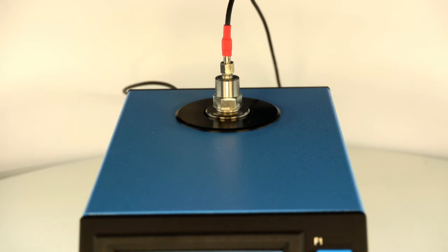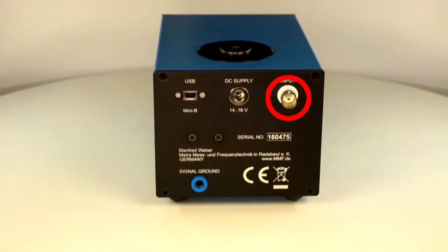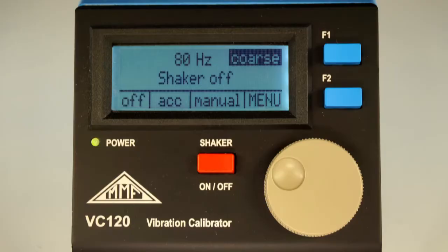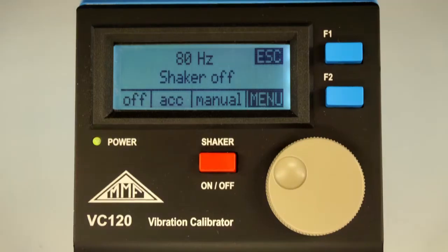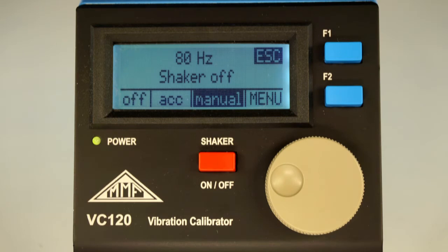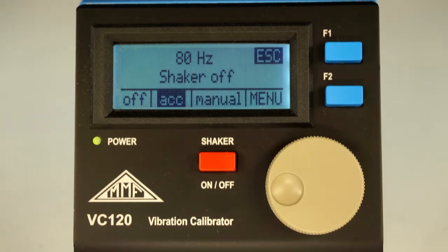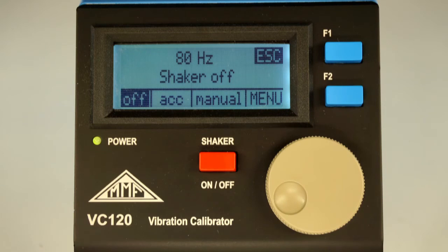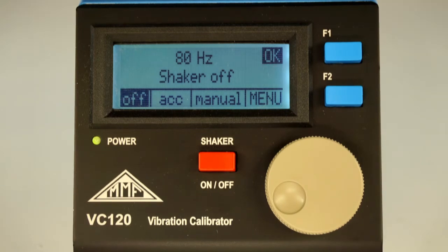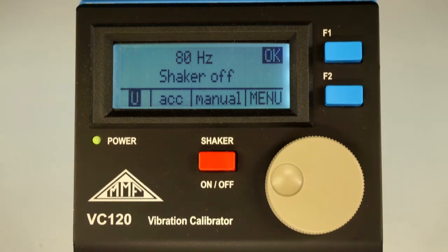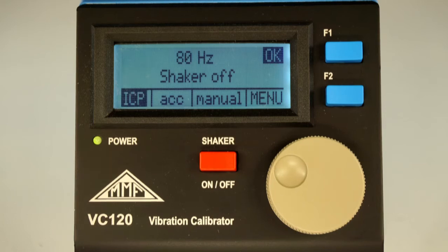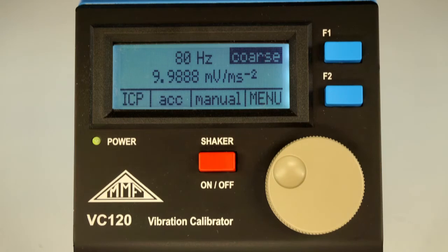Connect up the sensor to the BNC input socket at the back of the instrument housing. Switch the instrument on by pressing the red button. Press F2 to go to the menu. By turning the shuttle wheel and pressing F2 again, you can move across to the left menu item for selecting the input type. To select the input type, turn the shuttle wheel. You can choose from the following options: Q for charge, U for voltage, or ICP for IEPE. We want to calibrate an IEPE sensor and press F1 to confirm our choice.